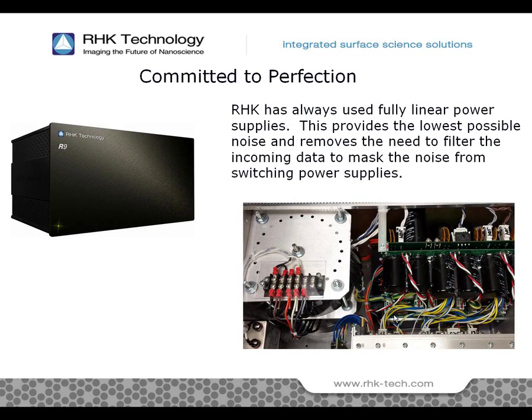To complete the R9, we knew that we needed to incorporate a linear power supply as we had done with the 8 generations of SPM 1000. These linear power supplies are heavy and expensive, but they're the only way to maintain the low noise levels that RHK is famous for. Without the high-frequency noise of switching power supplies, we did not need to filter out all the high-frequency signals coming from the microscope.